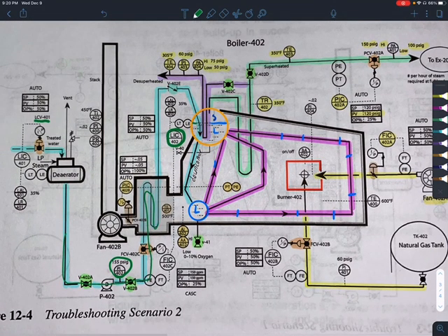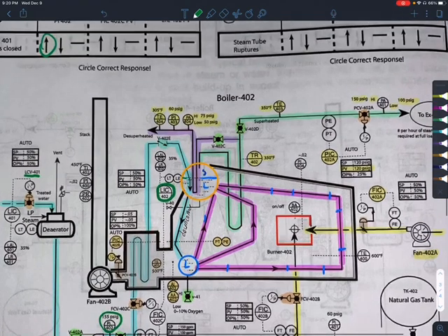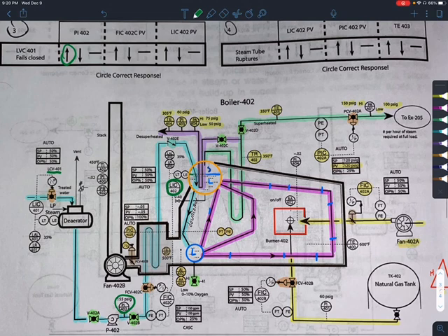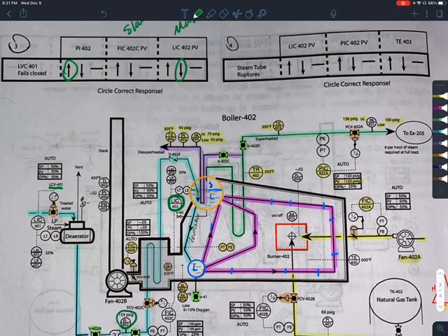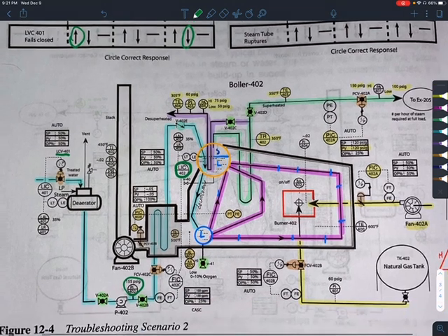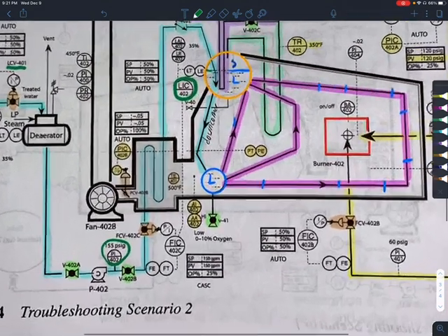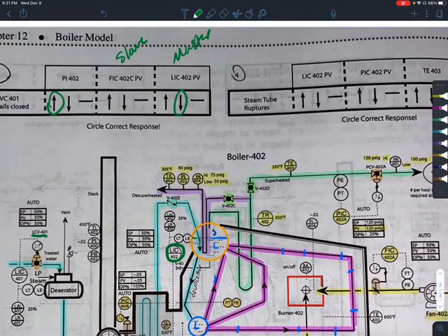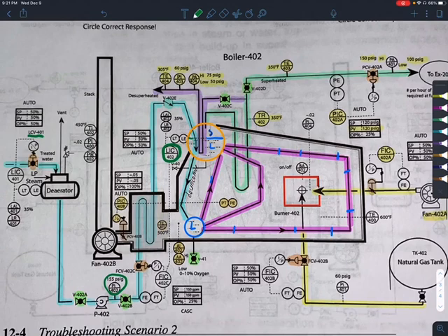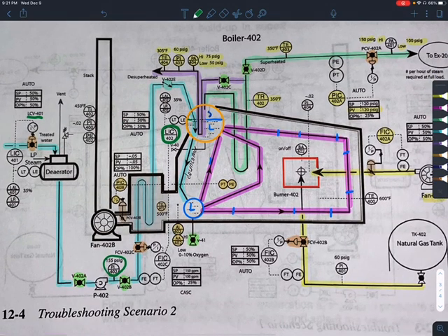I forget you guys can't see my pen. There's no flow going on, right? We remove that. So the level controller is going to read low. So that's going to go down. But because it's reading low, it's going to say, hey, we need more flow. Well, that's going to talk to the slave controller, FIC 402C, which is the next question, right? The process variable for it, the PV. It's going to say, hey, so it's supposed to be 50%, sorry, not 75%, 50%.